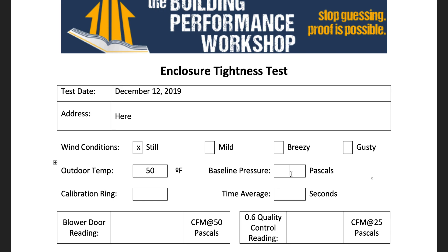Baseline pressure: if you don't know how to run the baseline function on your manometer that you're using for the blower door test, you need to stop watching right now and go learn how to do that, because this is very important. Let's say that the baseline pressure was 5 pascals. That means that when we run it to 50 pascals, we're actually going to be running it to negative 45 pascals, not negative 50. If you don't know how to do that function, you need to go investigate that further.